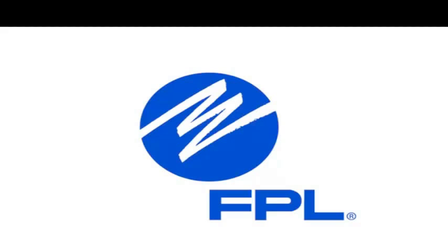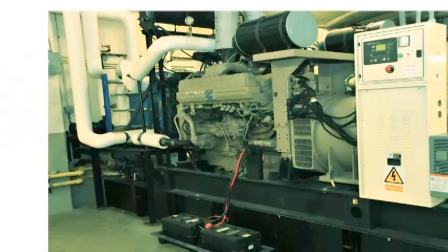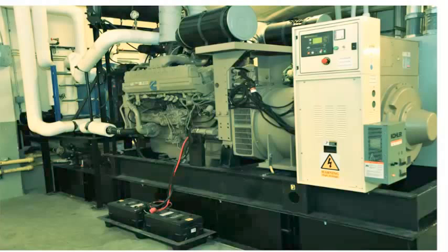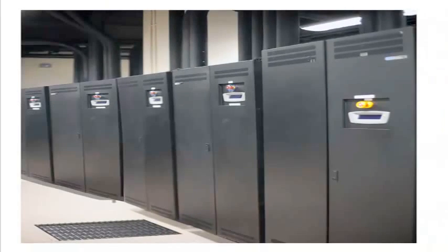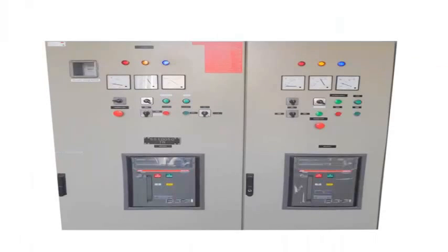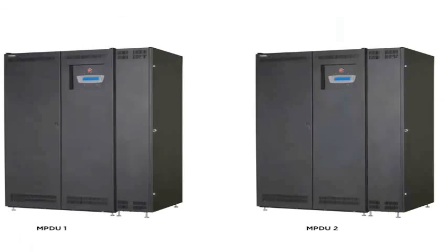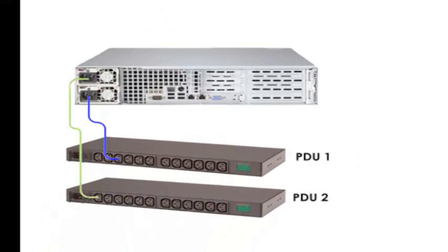So going back from the top to the beginning, we have direct power from our local electricity provider in Florida, as well as our backup emergency generator, going to our UPS bay. The UPS bays then connect to the ATS, which transfers the power to our master power distribution units, which then transfer to PDUs to get to your rack and of course your server.